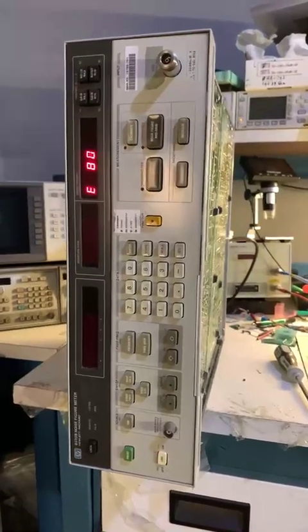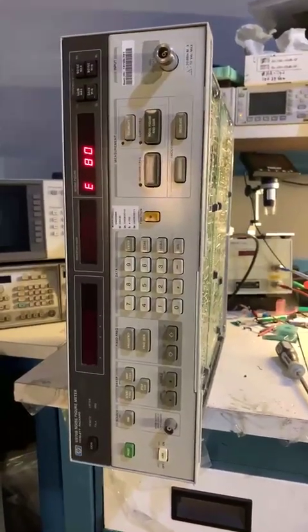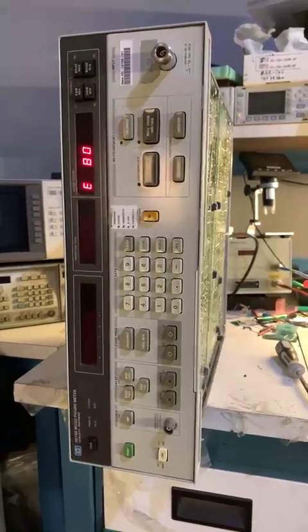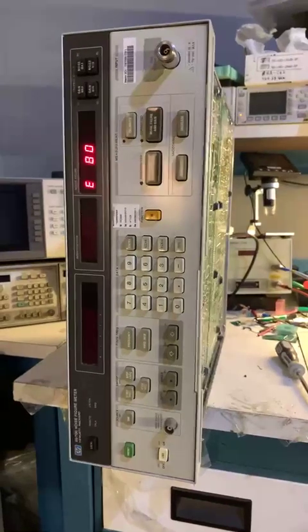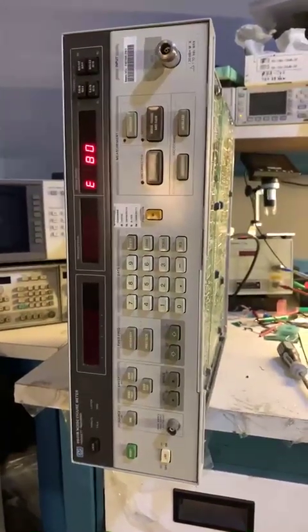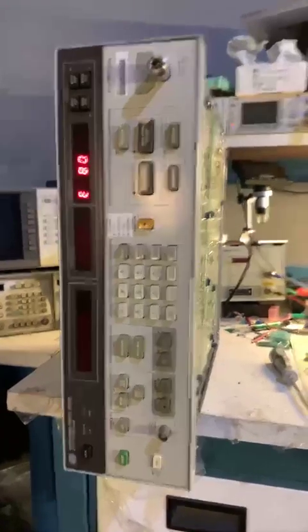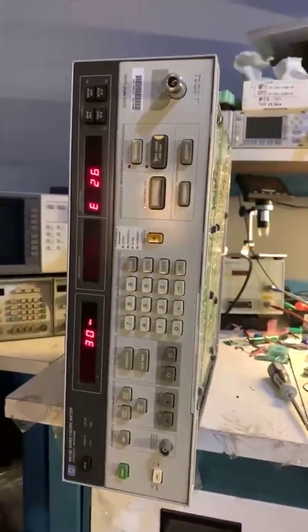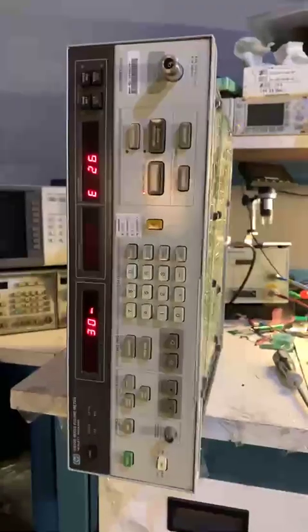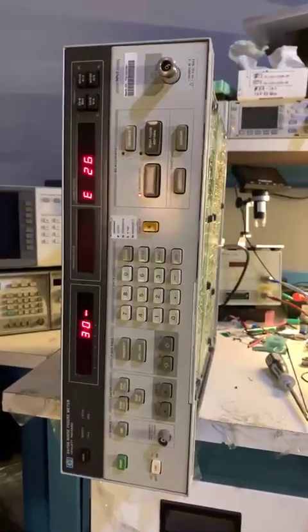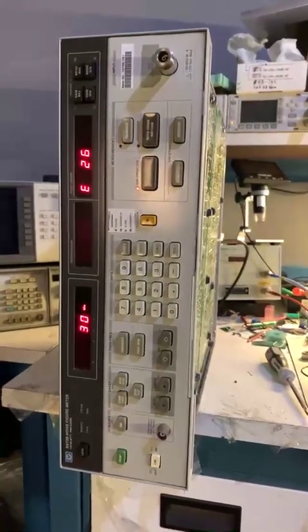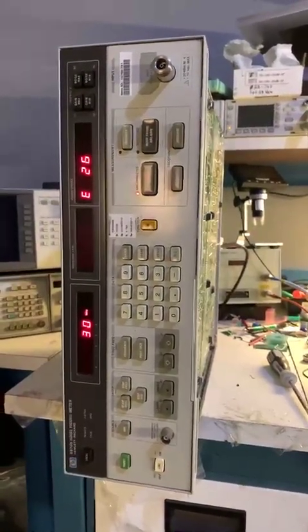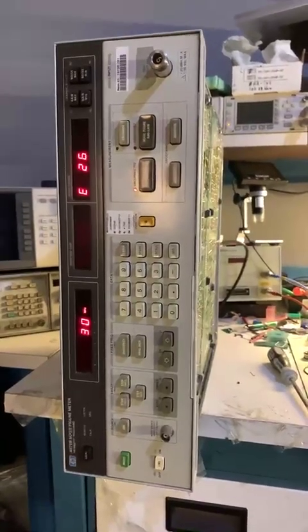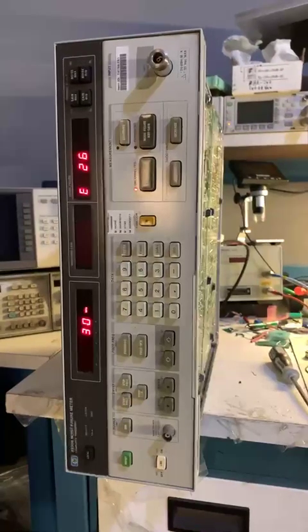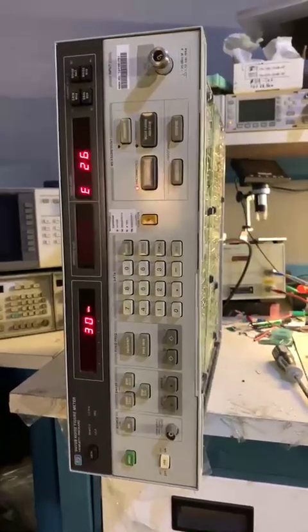those units, a lot of them come up with several error messages when you power them up, and one of them is error E80, which also usually appears in conjunction with E26. So if you push the button here, see now it's come up with E26. So those two normally go together. And what E80 means is that the internal battery of the unit has been depleted, is out of energy, and that basically the calibration memory of the unit has been lost.